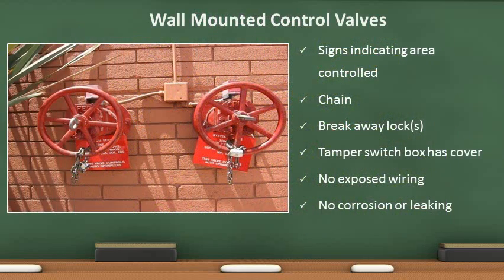These are wall-mounted control valves. They perform the same function as the control valves on the previous slides and have the same requirements. Signs indicating the buildings served shall be posted on or near the valves, and chains with breakaway locks are required. Again, there should be no corrosion or leaking, and no exposed wires.